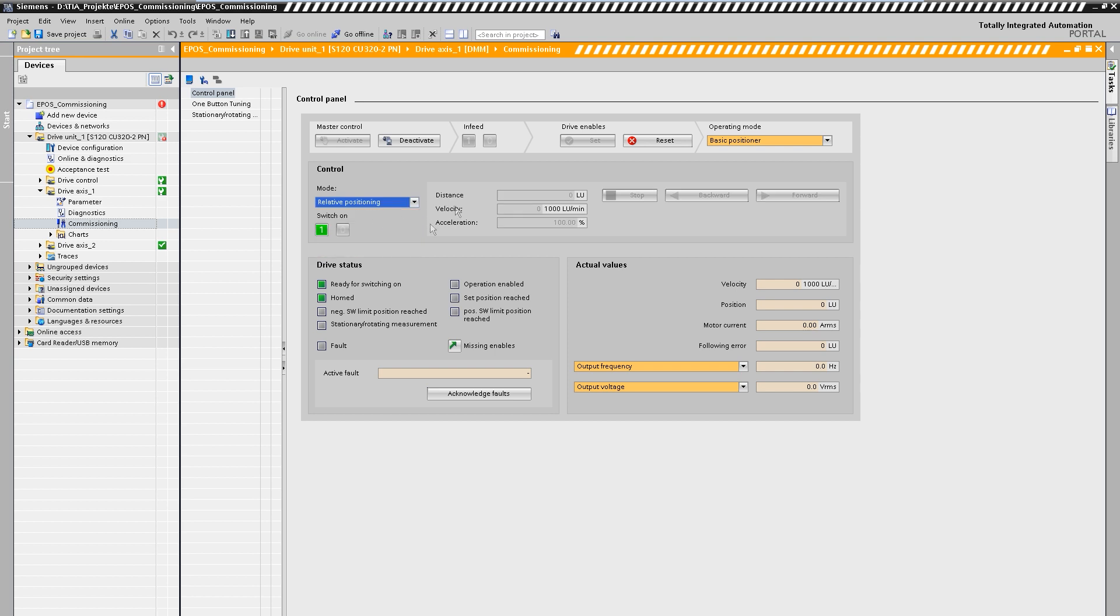We switch on the axis and enter the setpoint values. We want to perform a relative positioning of 100 millimeters. With our position normalization in micrometer this corresponds exactly to 100,000 LU. In addition we determine the traversing speed and start positioning.